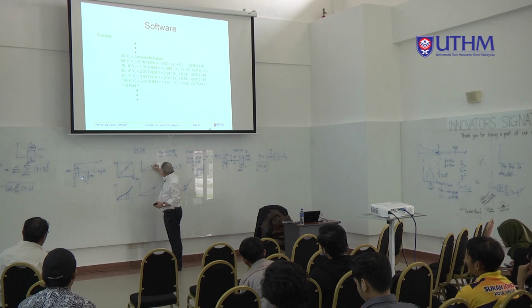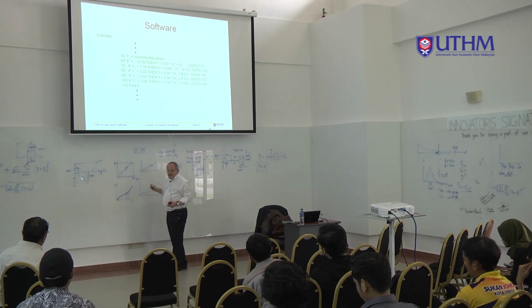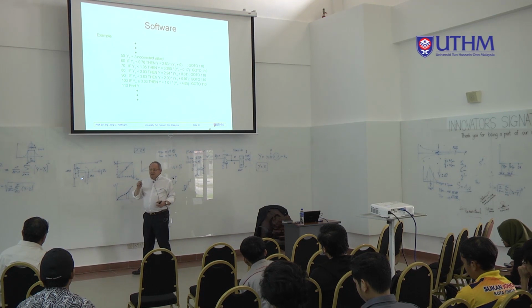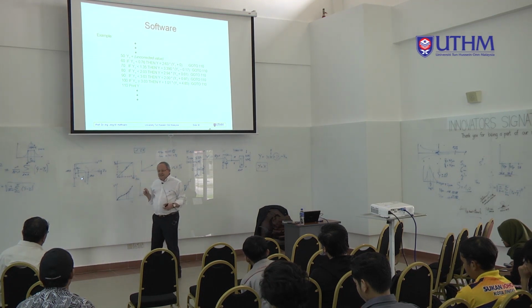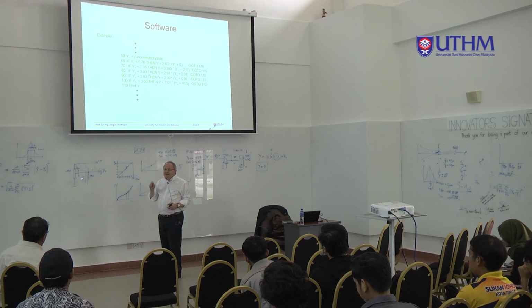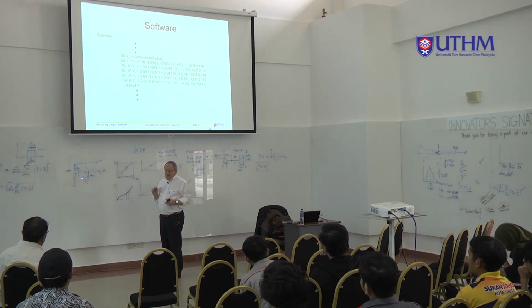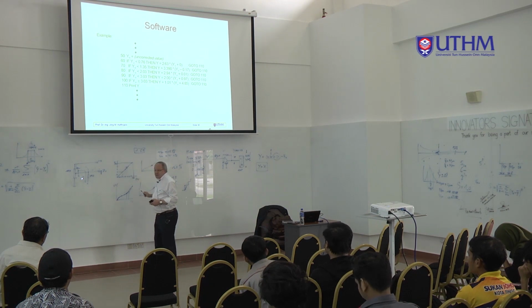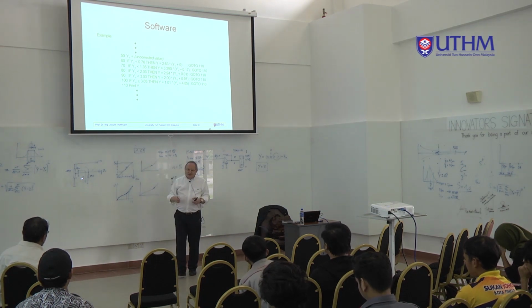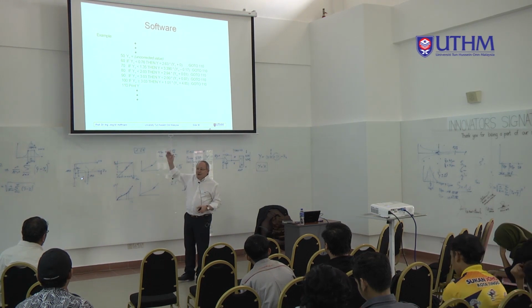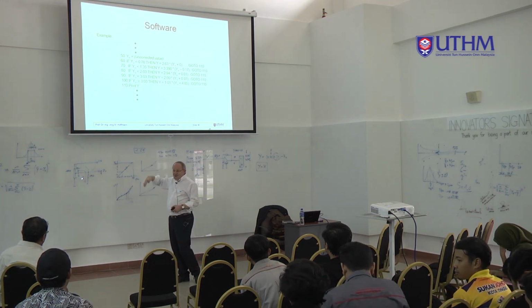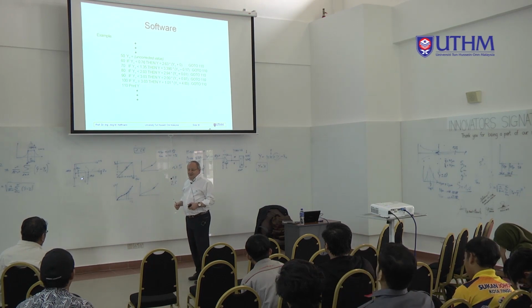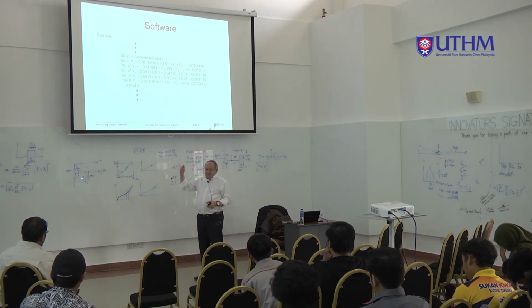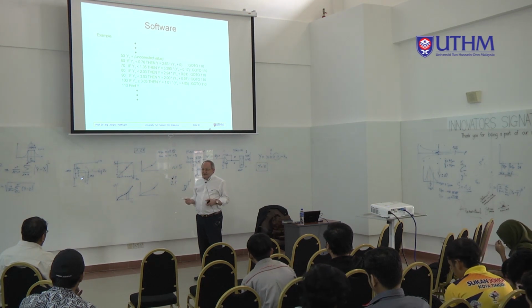And the question is, how big are these disturbances? It makes no sense to use an ADC with 16-bit, where 1 bit is, I haven't calculated it now, but maybe 1 bit is 1 nanovolt, and the noise from your sensor is a microvolt. Then you jump in your resolution of the 65,000 steps, and that makes no sense.